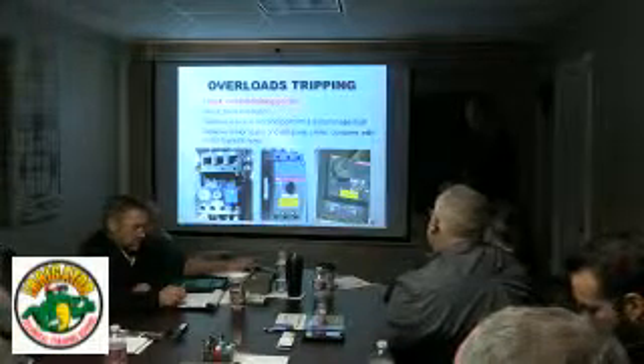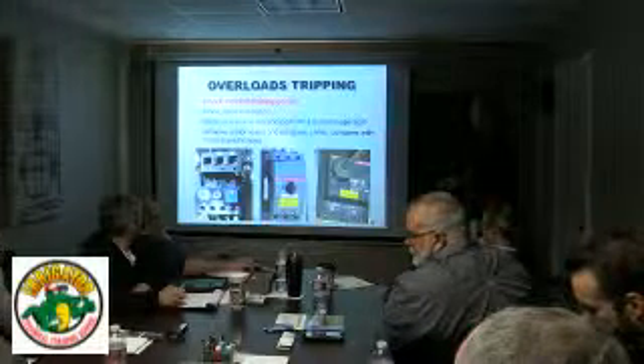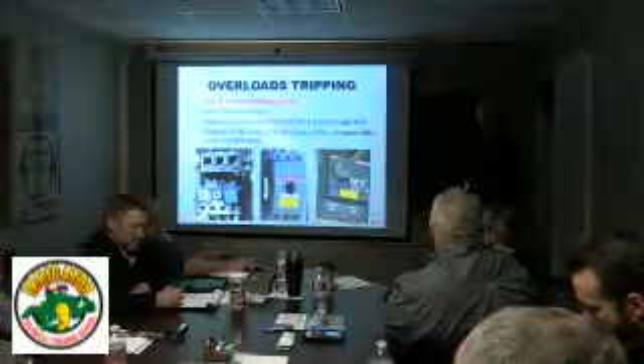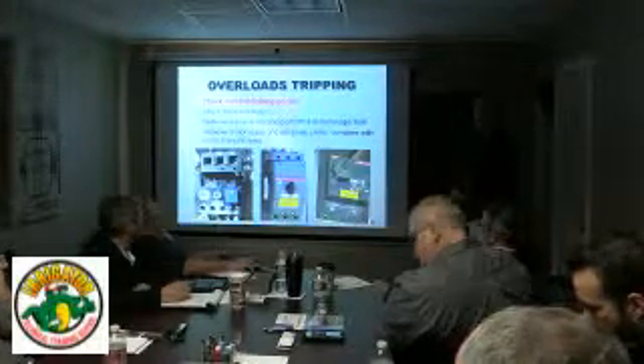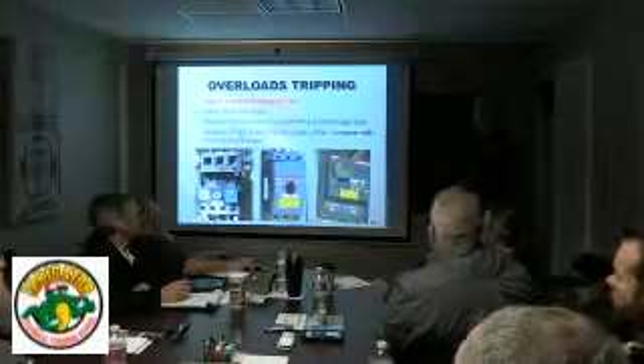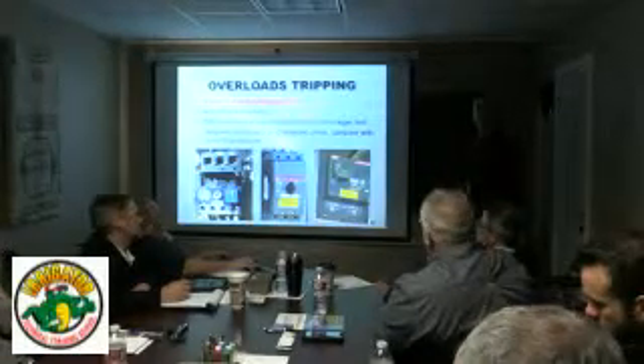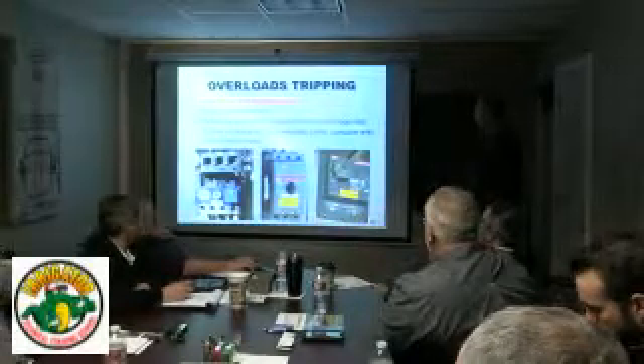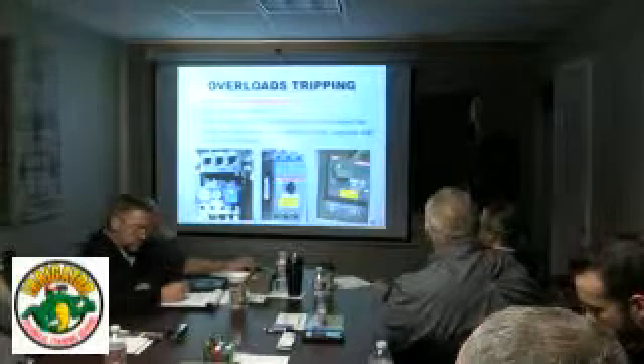Then we have another one, like the one we were just looking at. This one, if it's in the 12 o'clock position, it's on, and if it's in the 9 o'clock position, then it's off. But if it's halfway in between, about 10:30, that means that it's tripped. So if something's dead, you open the panel door and you see that sitting at about the 10 o'clock position, that means that overload's tripped. So then just start tracing the output there to try to find out why it may have tripped.